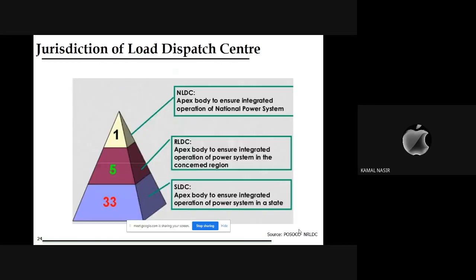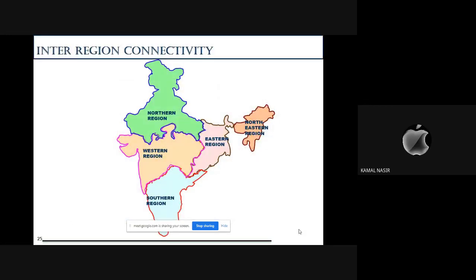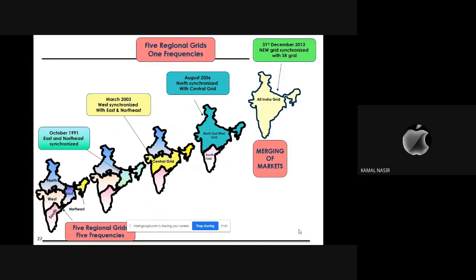This parameter was brought, we call it unscheduled interchange. We have already managed the grid for scheduling 24 hours, or 96 time slots, before. Now, if there is any variation in that scheduling, that has to come into place as unscheduled interchange. Now, this unscheduled interchange part will be either plus or minus. So, fixed cost plus variable cost plus minus UI.